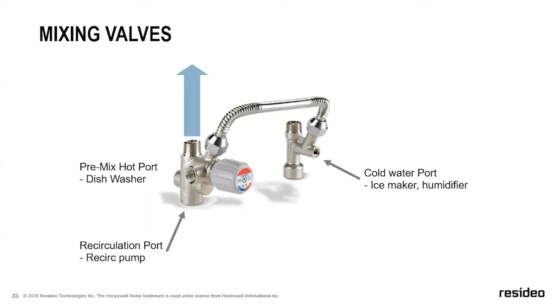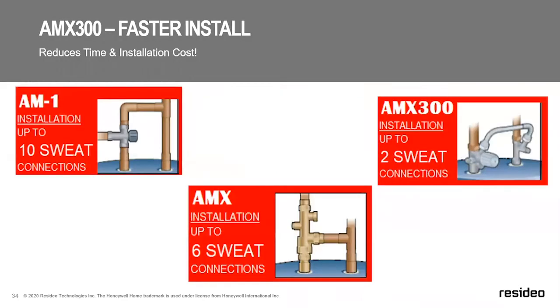And then we have a recirculation port up on the top on the left side there. So what that would be used for is if you have a recirc loop, you could pipe it right into there so you can have some on-demand hot water throughout your home. The set point knob right there with the gray knob is where you would make your adjustments. It does come with the thermo strip in the box, so you know exactly where you're setting the mixing valve to. We also have other mixing valves.